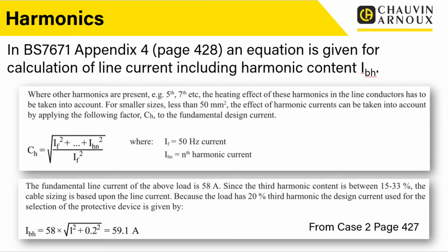The cable sizing is based upon the line current. And we'll look at that in a table in a moment. It's slightly out of sync here. Because the load has 20% third harmonic, the design current used for the selection of the protective device is given by this. So what they do is they take the design current, and multiply that by the square root of 1, the fundamental, plus 0.2 for 20%, both squared and added together. The square root of that gives a value for IBH of 59.1 amps. So you can see with the 20% third harmonic content, the design current has gone from 58 up to 59.1.